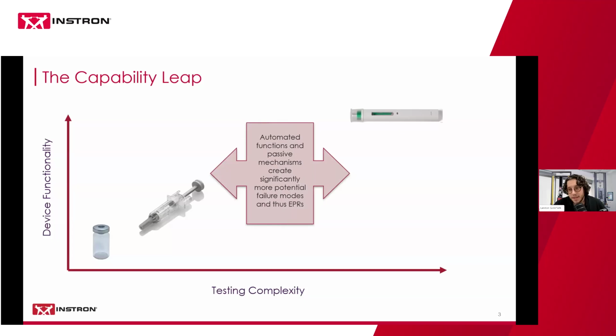And the biggest thing for us is that there is such a massive leap in capabilities between a pre-filled syringe and an auto injector that change how this device has to be tested. These devices have significantly more automated functions that all have to be checked to make sure that they are performing accurately and reliably. They have passive safety mechanisms and passive mechanisms that tell a patient whether the injection worked or not, whether the injection is complete, that lock out the device. These are all things that have to be confirmed after a device is tested.